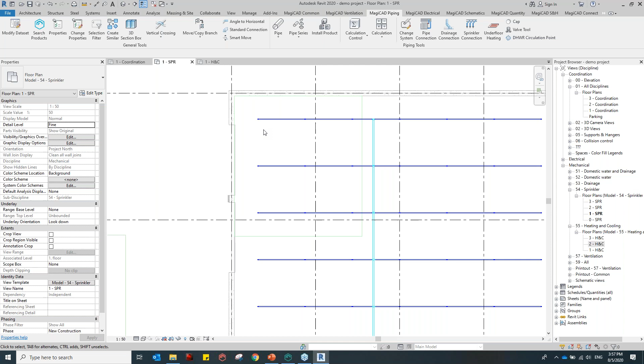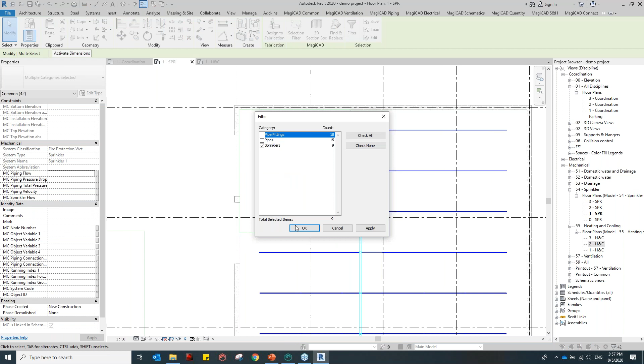Then what I need to do is make sure that, for example, I select these and then filter only sprinklers. And all the sprinklers that I'm going to use have a coverage area. Coverage area is 9 meters square or 12 meters square. For example, I put 9 meters square, and the design density is 7.5, which is very high. And just use that, and 100 kilopascal, which is 1 bar. So this is the basic information that you need to put in.